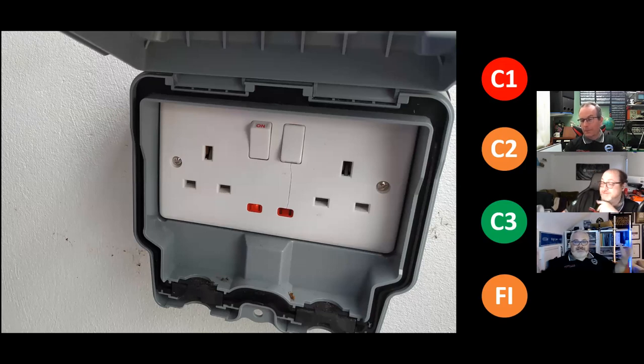So the lid was up. So the IP rating is obviously an issue that needs coding. And obviously, was there evidence of the cause of this? Was it just an impact? There was an extension lead plugged into this, but there was nothing plugged into the extension lead. And the extension lead was trailing outside on some decking, and that actually was full of water, which obviously showed up as a fault. When it was unplugged, the insulation resistance showed perfectly fine, bar the neons, obviously.